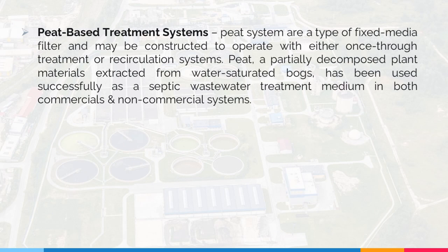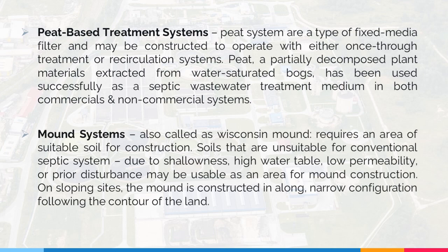Peat-based treatment systems are a type of fixed media filter and may be constructed to operate with either once-through treatment or recirculation systems. Peat, a partially decomposed plant material extracted from water-saturated bogs, has been used successfully as a septic wastewater treatment medium in both commercial and non-commercial systems. Mound systems, also called Wisconsin mound, require an area of suitable soil for construction. Soils that are unsuitable for conventional septic systems due to shallowness, high water table, low permeability, or prior disturbance may be usable as an area for mound construction. On sloping sites, the mound is constructed in a long narrow configuration following the contour of the land.